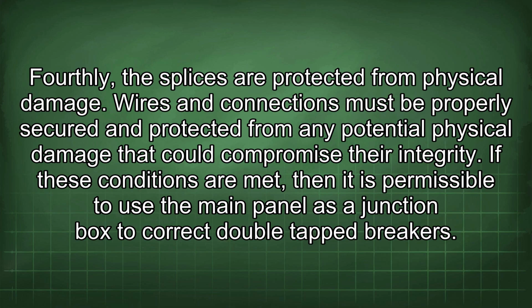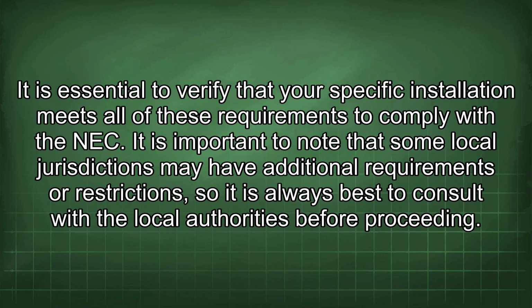If these conditions are met, then it is permissible to use the main panel as a junction box to correct double-tap breakers. It is essential to verify that your specific installation meets all of these requirements to comply with the NEC. It is important to note that some local jurisdictions may have additional requirements or restrictions, so it is always best to consult with the local authorities before proceeding.